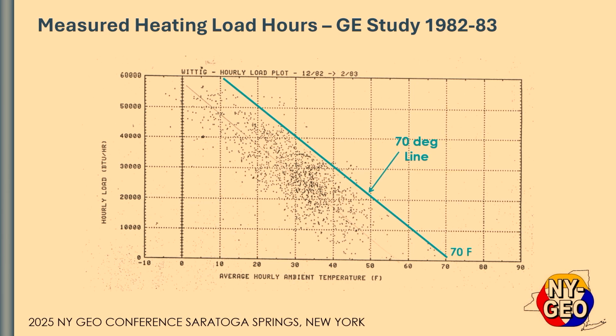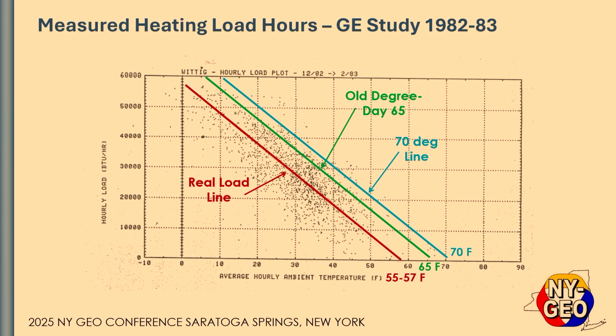And so you would have expected it to be from 70 degrees on down, but obviously the dots don't quite line up with that. If you've ever done a heat loss or heat gain calculation, you know that most of the time we've used what's called the old degree day method, which was based upon 65 degrees, and it's a little bit closer, but that was set in the 30s back when heat loss and heat gain calculations first began. Homes weren't insulated very well. They were kind of loose, and so 65 isn't very accurate for today. What is more accurate for today's homes is in the 55 to 57 degree range.